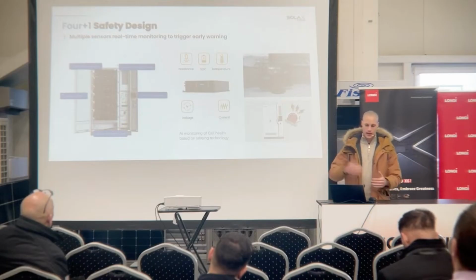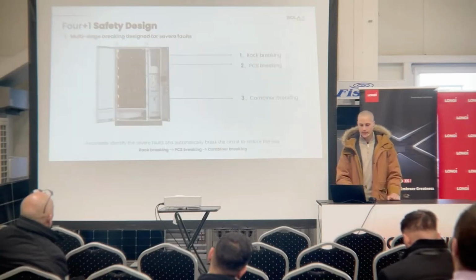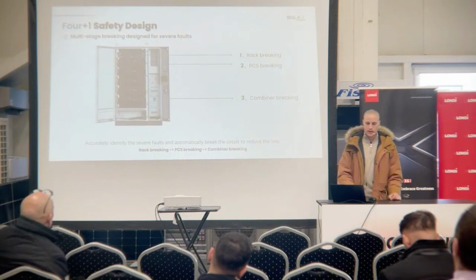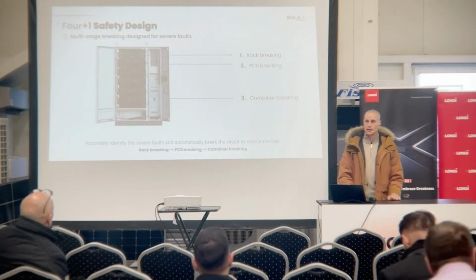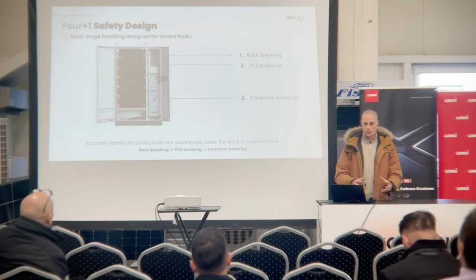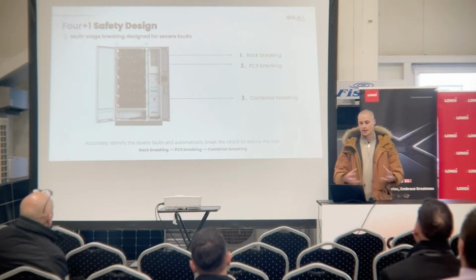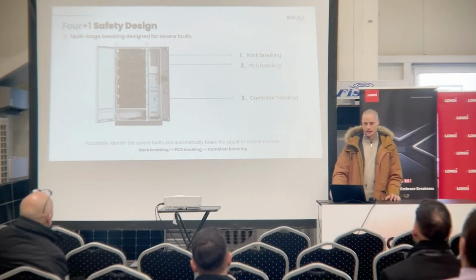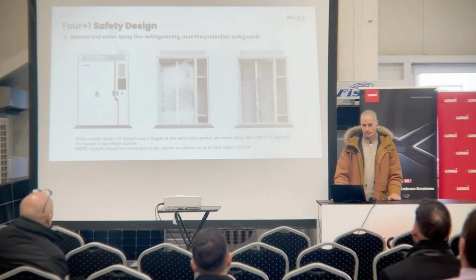And if that error or fault gets to a more serious level, then the ESS can turn itself off from the AC and DC side, physically turn off, in order to stop working and maybe to prevent a possible fire inside the battery pack. And if the switching off is still not enough, then of course the aerosol and the water spray will start to work, and it will try to suppress the fire inside the cabinet.